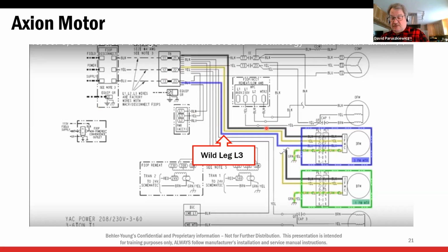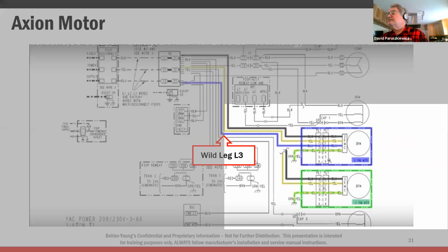Okay, so there's power to those motors all the time. So that's pretty easy to check that motor, right? I could check for voltage right here. All right, I can take my voltmeter. Motor's not running. I can go right to the motor and check for line voltage. Right here on a 3-phase, right here on the single phase.